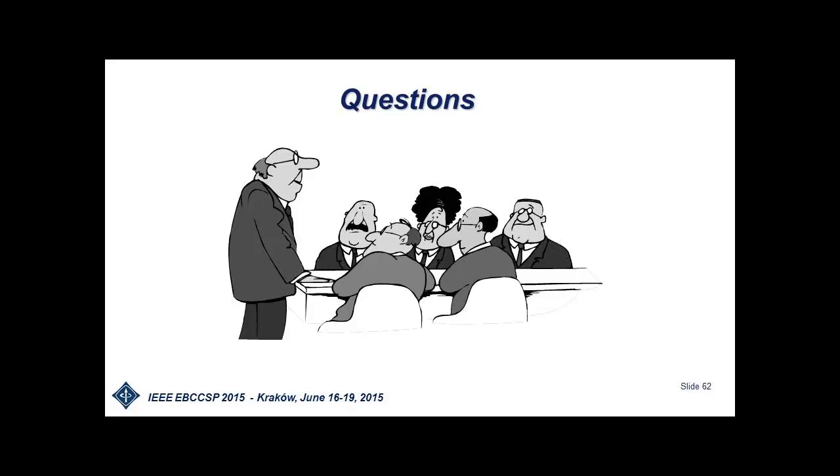Thank you. I guess, Terry, the straight answer is that if it's periodic, you can use PIDPlus and do a good job there. Oh yeah, you can. It's really nice in that it's like a continuum all the way from regular wired up. Only once you get past about 30 seconds do you get into the situation where you really don't need to be using PIDPlus. You could use regular PID, but that window of 0 to 30 seconds is really where it has its major benefit.